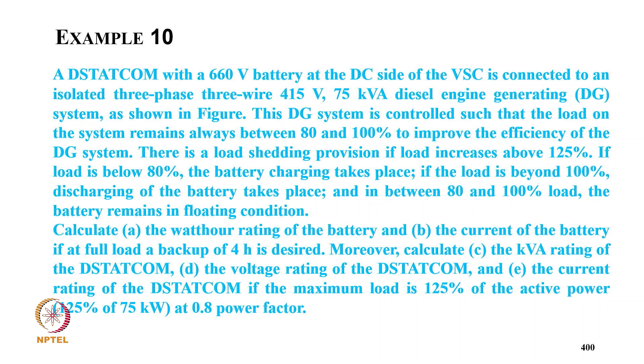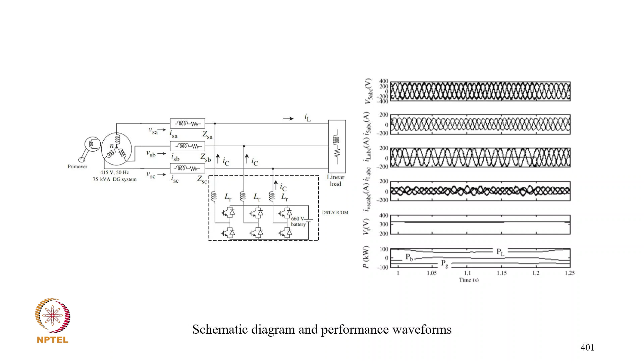If the load is beyond 80 to 100%, discharging of the battery takes place, and in between 80 to 100% load, the battery remains in floating condition. Calculate the rating of the battery and the current rating of the battery, if a backup of 4 hours is required. Moreover, calculate the kVA rating of the DSTATCOM, the voltage rating of the STATCOM, and the current rating of the STATCOM, if the maximum load is 125% of active power of 75 kW at 0.8 power factor. This is a typical diagram that you have, a 75 kVA DG system with a DSTATCOM with the battery on the DC side, with the load, and these are the typical simulated equipment.